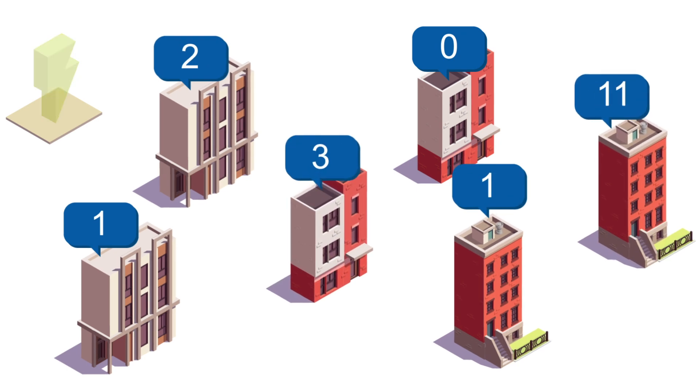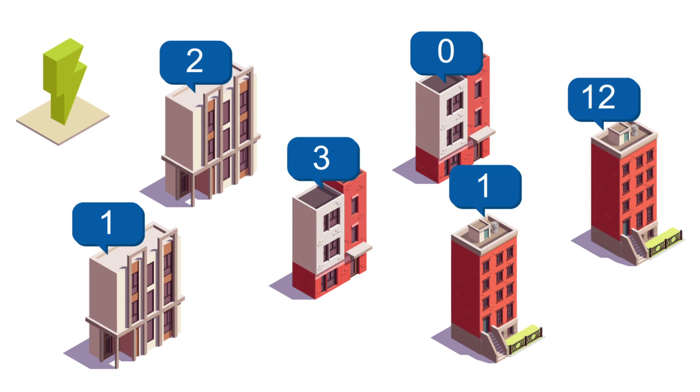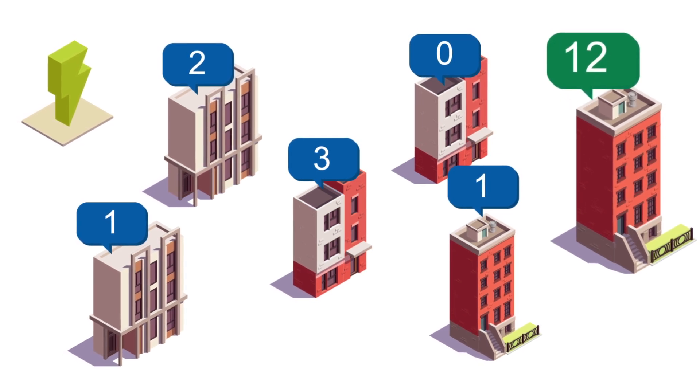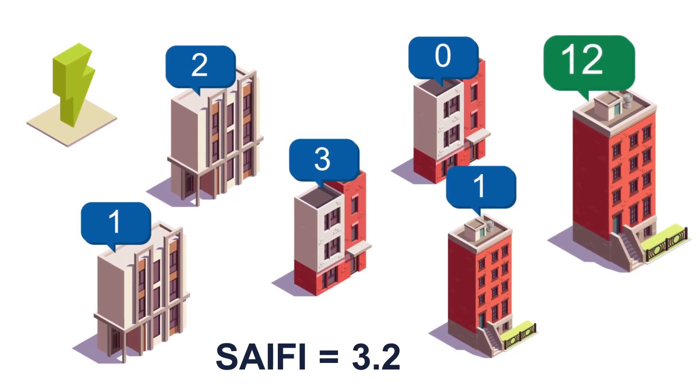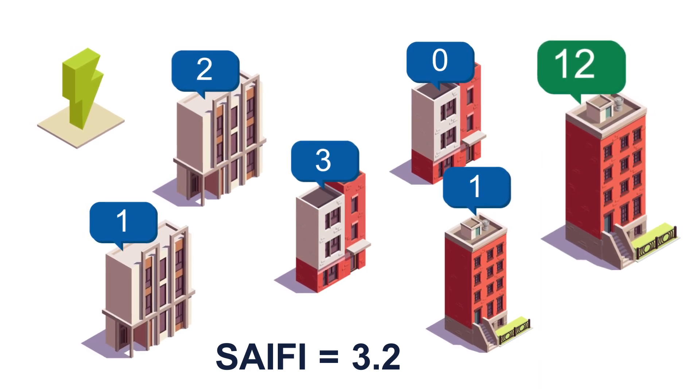CEMI provides a more complete picture of system performance because it tracks customers with the worst experiences — data points that aren't visible when averaging interruptions across the system, such as in common metrics like SAIDI and SAIFI. Even in areas where regulators don't monitor CEMI, every line crew knows the houses they must visit again and again.